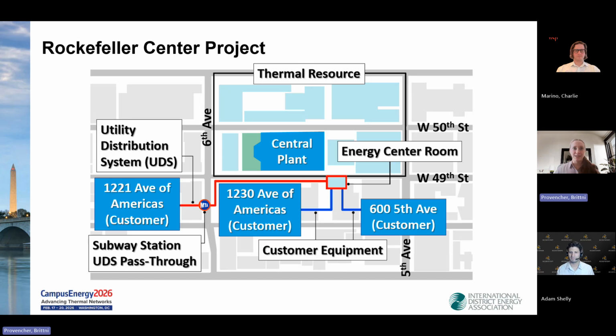So Con Ed's Rock Center project captures waste heat from a large interconnected campus of buildings in Midtown Manhattan and distributes it to 3 large commercial office buildings by installing about 8,000 linear feet of piping. The 3 customer buildings will use modular water source heat pumps to convert a portion of their heating systems from steam to the UTEN. This UTEN is heating only, and it's an ultra-low temperature hot water system with the temperature in the utility-owned piping varying from 80 to 92 degrees Fahrenheit.